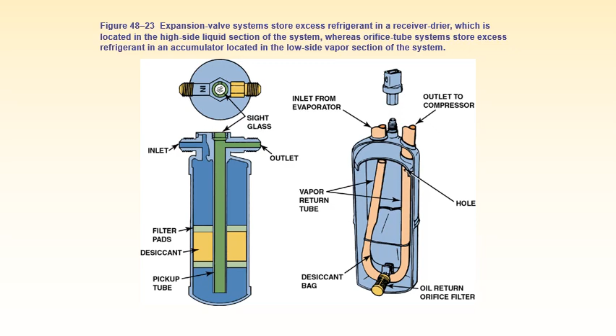Now next important thing is the accumulator. An accumulator is used in the orifice tube type of system, and it is located between the evaporator and the compressor. Refrigerant in this section of the cycle is a low pressure gas, and the purposes of the accumulator are preventing liquid refrigerant from reaching the compressor, holding the reserve of refrigerant, and holding the desiccant which is used to remove the moisture. Take an important note, a liquid cannot be compressed, therefore the liquid which is entering the compressor must be removed, otherwise it would cause lockup or damage of the system.